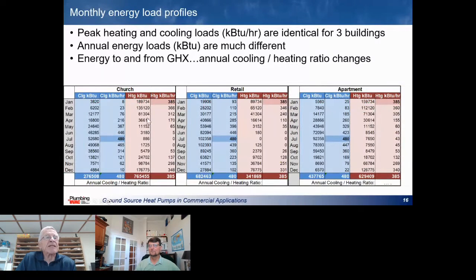But what's missing is the number of hours that system is going to run to cool this building, or this building, or this building: church, retail store, and apartment building. This one's going to run a lot fewer hours in cooling because it's only used a few times a week. This one is going to be running a lot more hours because that store might be open for 12, 14, 16, 18 hours a day. And there's a lot of people running around in the store, lights on, so it's going to force that same 40 tons to run a lot more often. And the apartment is probably somewhere in between, just about right. Even though the peak loads are identical on all 3, the energy loads are quite a bit different.